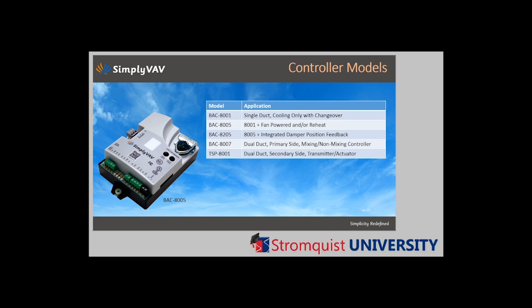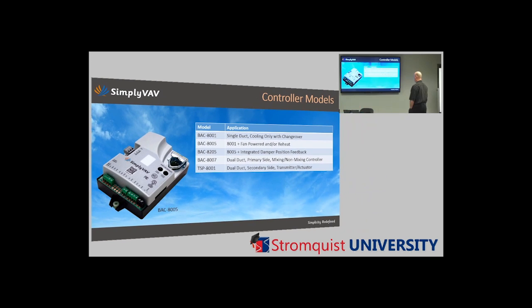Available in a few different models. There's a single duct cooling only model, very popular. There's a fan-powered reheat model. There's a model that's available that has integrated damper feedback position if you need that. And there are a couple of dual duct flavors available. Dual duct is not real popular, but you do run into those occasionally. And when you do, this gives you a cost-effective way to approach it from a retrofit perspective.